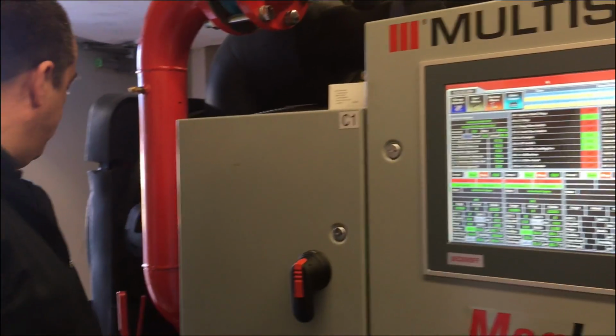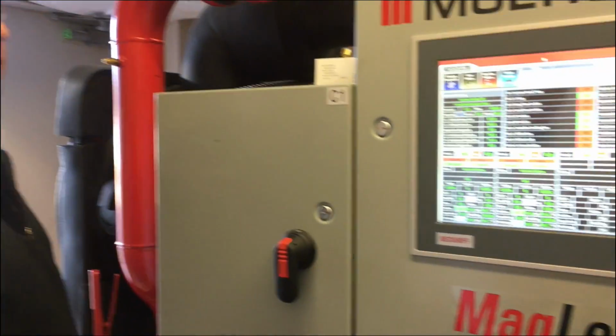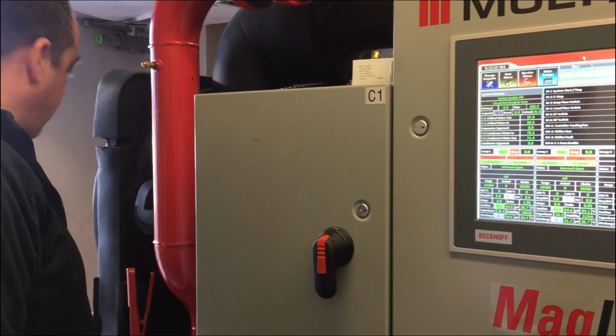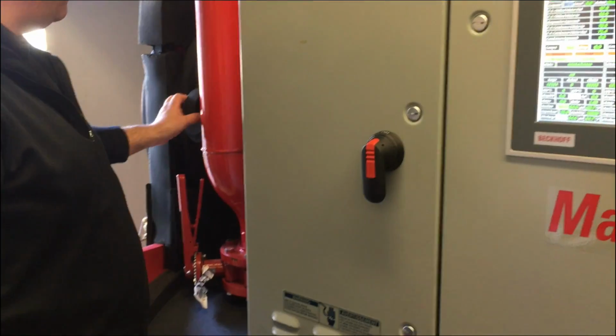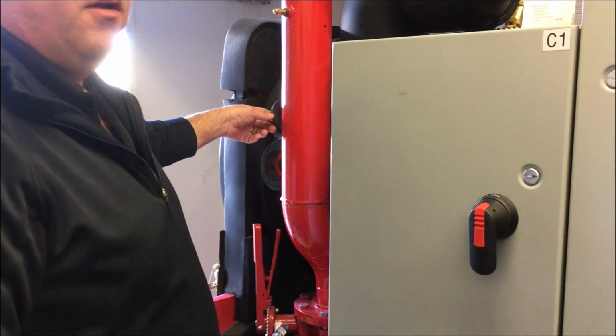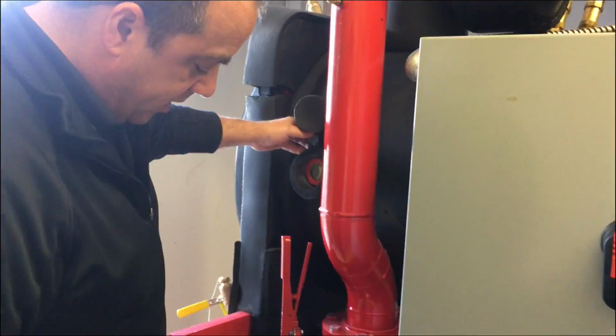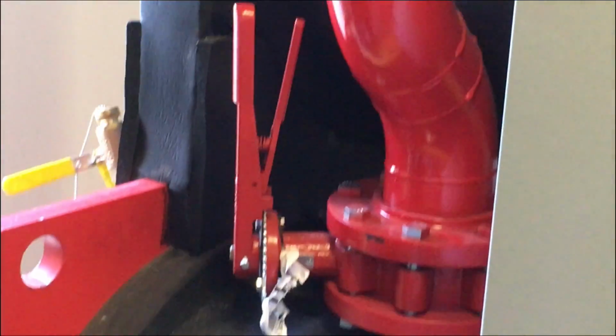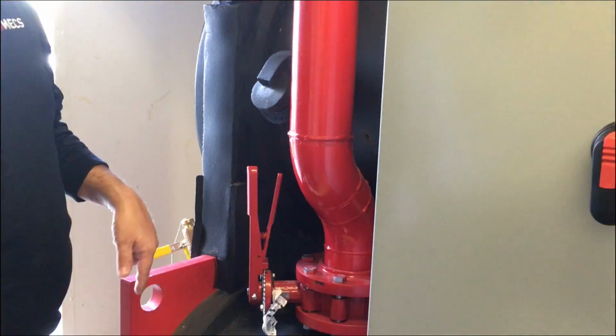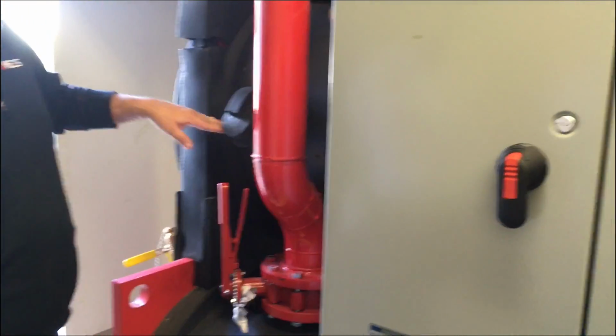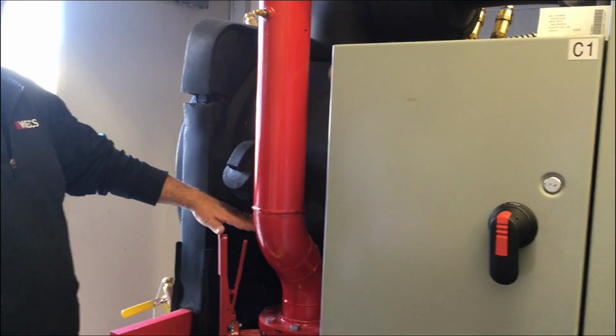Let's see. We have components on this side before we flip to the other side. We have the sight glass for the evaporator and the sight glass for the condenser. So essentially at full load, you'll see refrigerant in both. At low load, you'll usually always see refrigerant in the condenser, but if it's not drawn hard enough, this refrigerant is going to sit a little lower in this evap.